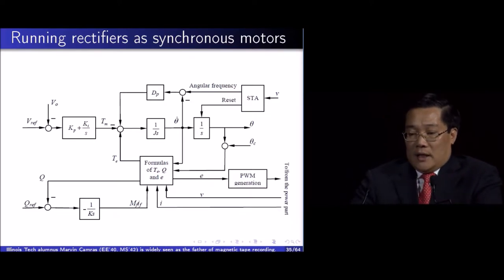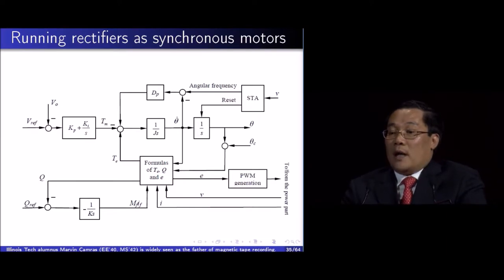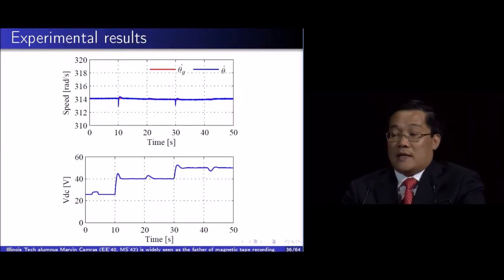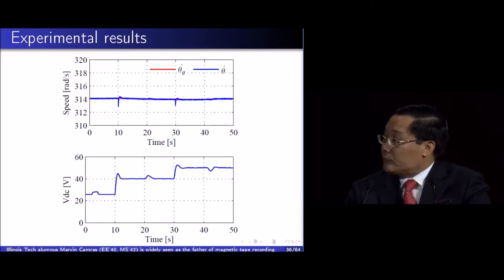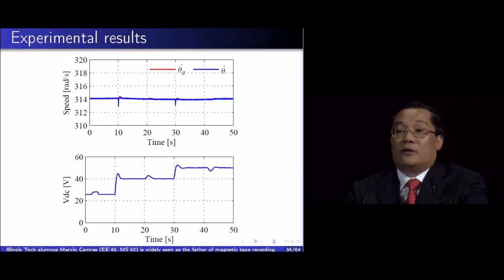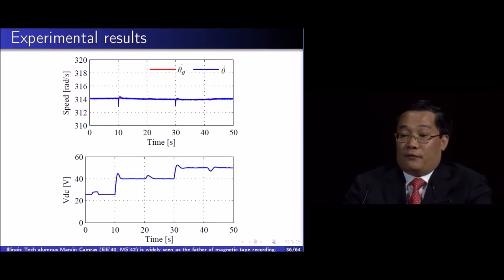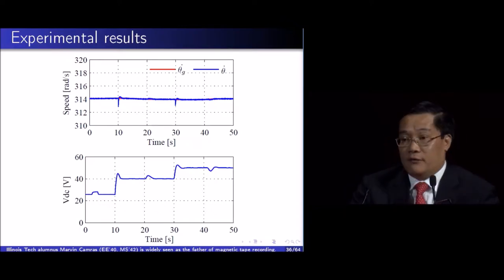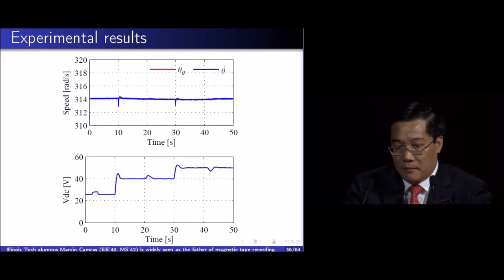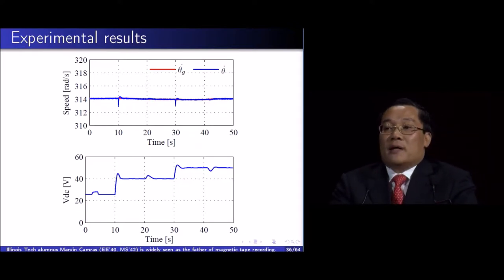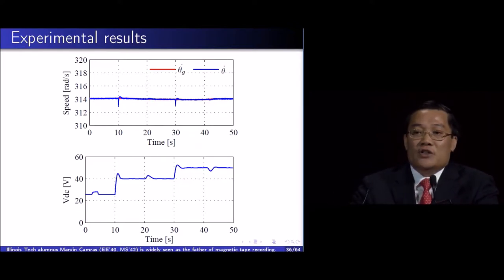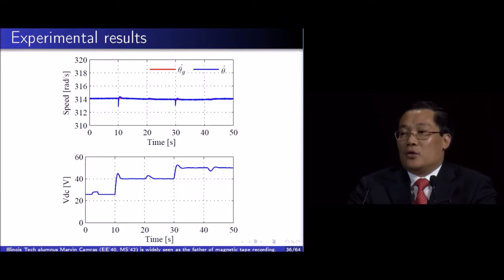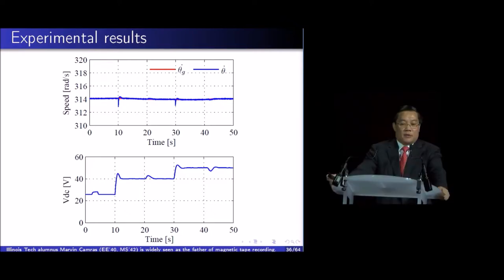We tested this in the lab and found it works as expected. The blue line in the first curve is the frequency inside the rectifier, and it follows the red frequency from the grid very well—so close they're difficult to differentiate. We were also able to regulate the DC bus voltage very well, confirming we can control rectifiers as virtual synchronous motors.